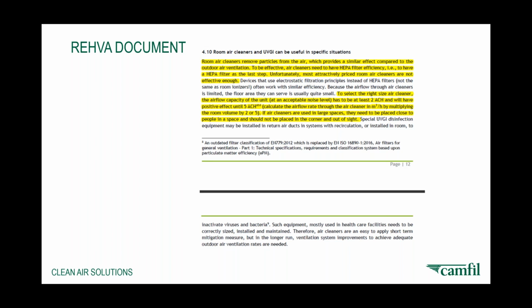But it's critically important that you choose a HEPA that is correctly tested and classified in the factory according to the standards that we'll discuss in a second. They also recommend that you select the right size air cleaner. You have to look at least 2 air changes and up to 5 air changes per hour. So you have to look at the airflow rate through the air cleaner and the size of the room, and then deploy the correct number of air cleaners into these rooms. So one air cleaner will not work in every room. It's not a one size fits all technology. You need to place them in the space where they can be visible, where they are recirculating air correctly, not put in the corner, out of sight, out of mind. It's got to be in a location where it can actually physically move the air through the HEPA filters and filter the air in the room.